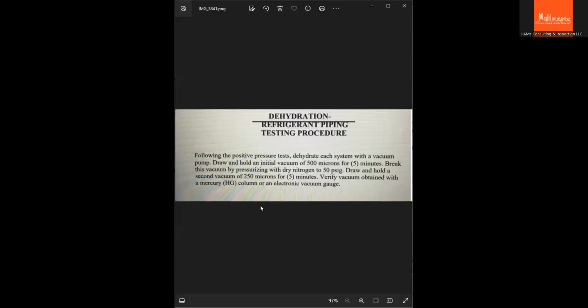This is the dehydration requirement. It is a two-stage test. After the pressure test, I have witnessed the 500 microns, the first stage of the test, then a break pressure of 50 psi. This 500 microns should hold for 5 minutes with no changes in the reading of the pressure gauge. And then the second stage will be 250 microns.